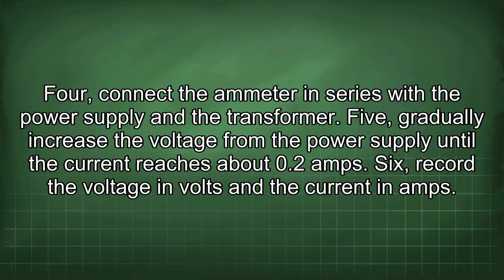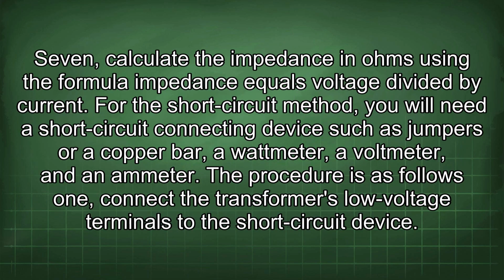5. Gradually increase the voltage from the power supply until the current reaches about 0.2 amps. 6. Record the voltage in volts and the current in amps. 7. Calculate the impedance in ohms using the formula impedance equals voltage divided by current.